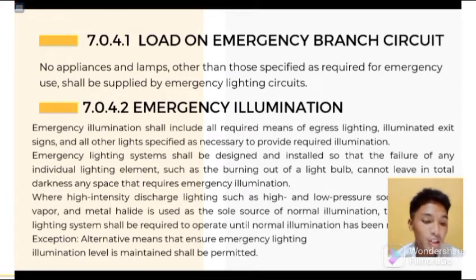7.0.4.2 Emergency Illumination. Emergency illumination shall include all required means of egress lighting, illuminated exit signs, and all other lights specified as necessary to provide required illumination. Where high intensity discharge lighting such as high and low pressure sodium, mercury vapor, and metal halide is used as the sole source of the normal illumination, the emergency lighting system shall be required to operate until normal illumination has been restored. The exception for this emergency illumination is alternative means that ensure emergency lighting illumination level is maintained shall be permitted.